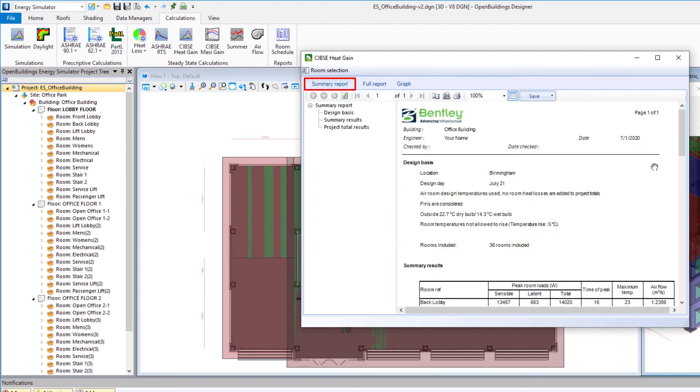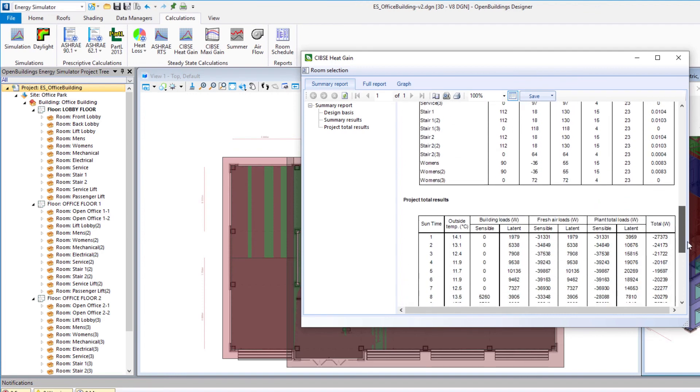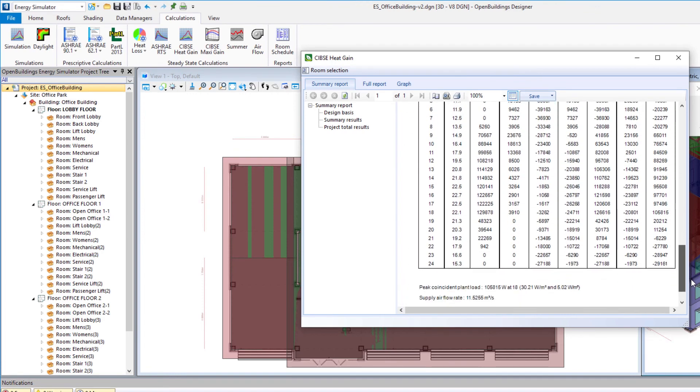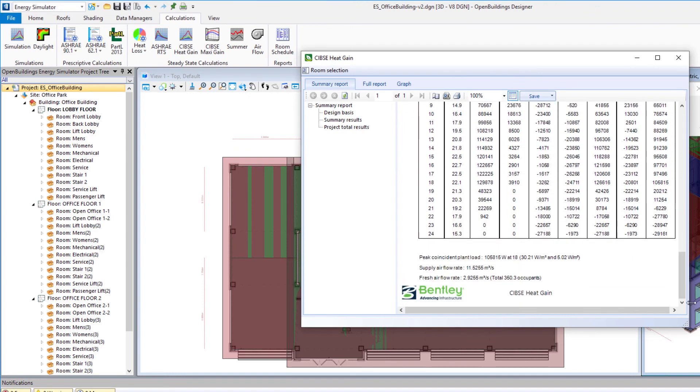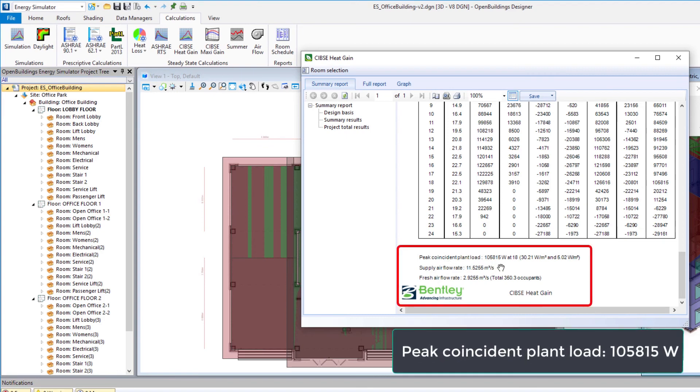And let's go back to that summary report as well. And we're going to scroll all the way down on the summary report. And note that it does give us our peak coincident plant load, supply air flow rate and our fresh air flow rate. And we should find that peak coincident plant load has decreased some because of that change we made to the fins.